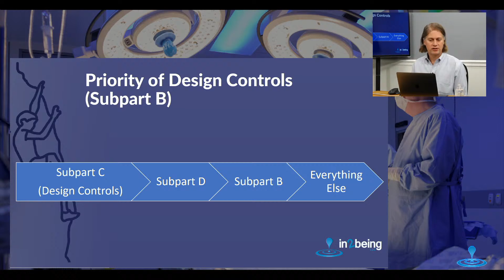Well, does this apply to all medical devices? That's a great question. Design controls, according to 820.30, apply to a few different situations. They apply to all Class 3 devices. That's a given. They apply to all Class 2 devices. Now, there may be places where exceptions can occur, but that's exceptionally rare. In general, they apply to Class 1 devices that are automated by computer software. So if you have automation using computer software in your device, even though you're a Class 1 device, you may not be subject to 510(k). But if you are automated by computer software, you will be subject to design controls.